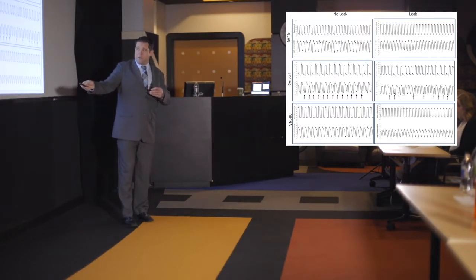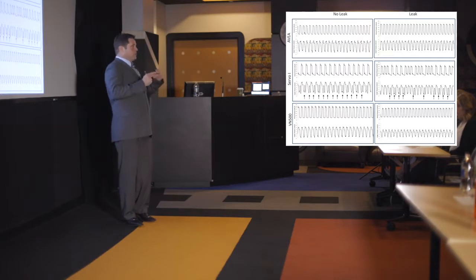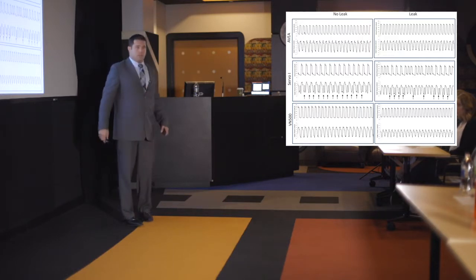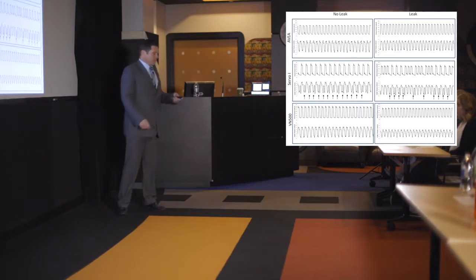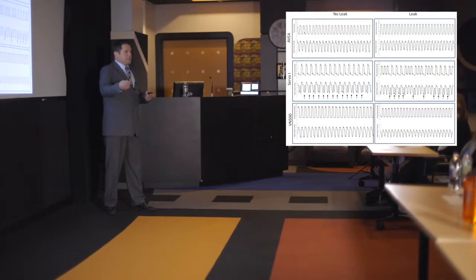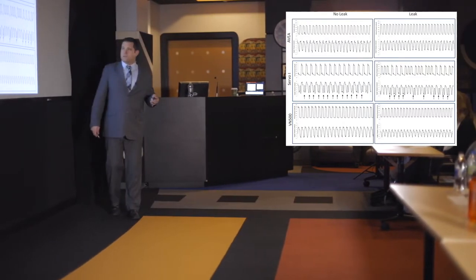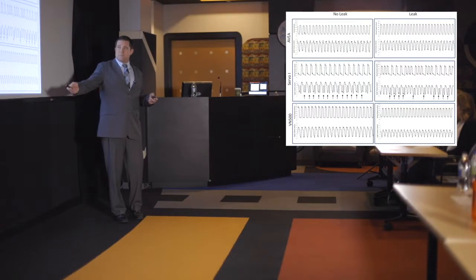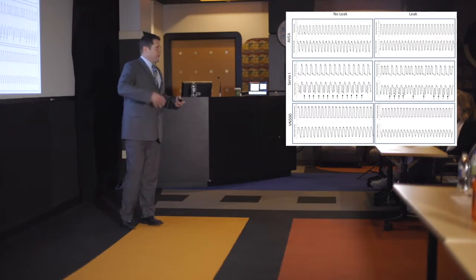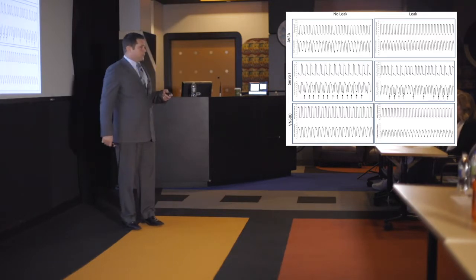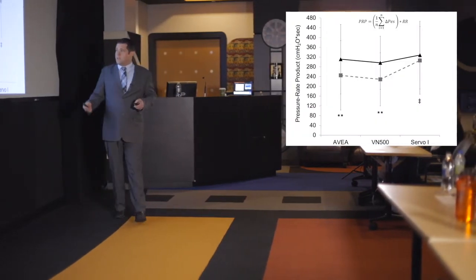But in the case of no endotracheal tube leak, they were generating 2 breaths sometimes. That's the pleural pressure, the esophageal pressure. They were generating 2 breaths in order to get 1. And so if you have NAVA, that's cool. Maybe they can trigger a little bit better. But I think with this new ventilator, things are going to be a little bit different for them. This just speaks to older technology and newer technology. I know that a lot of the ventilators are going down the same route by incorporating proximal flow sensors and using leak algorithms. This is work of breathing.